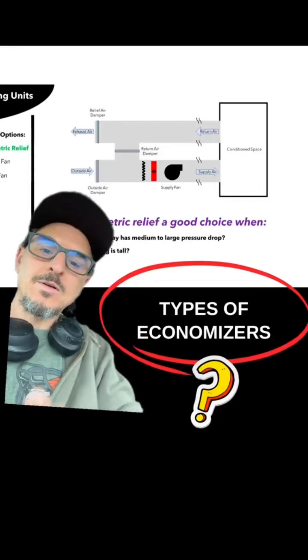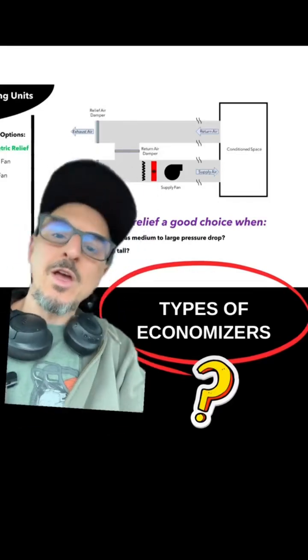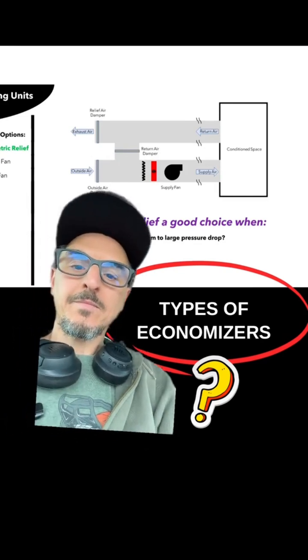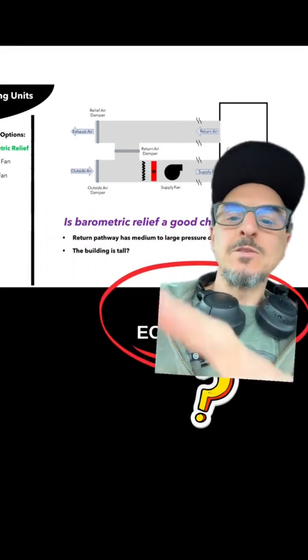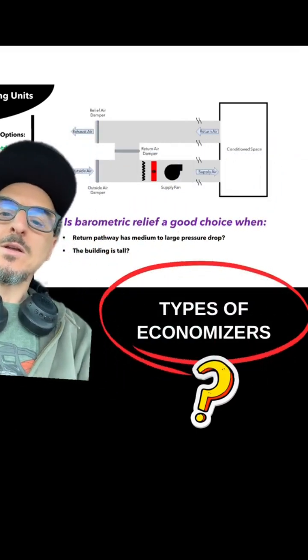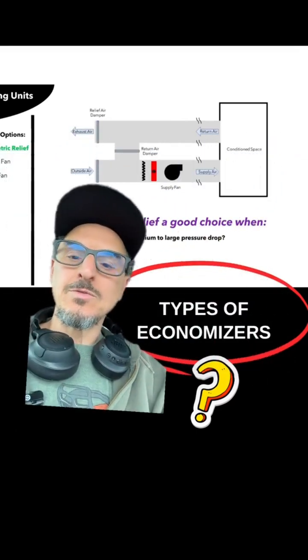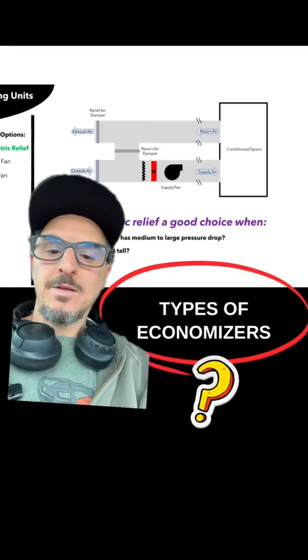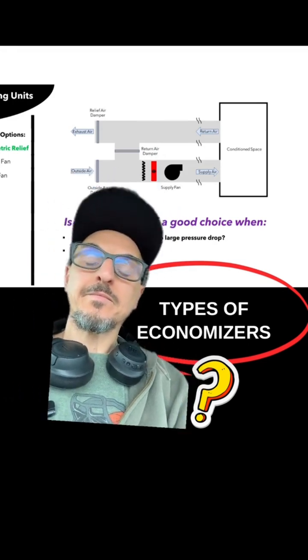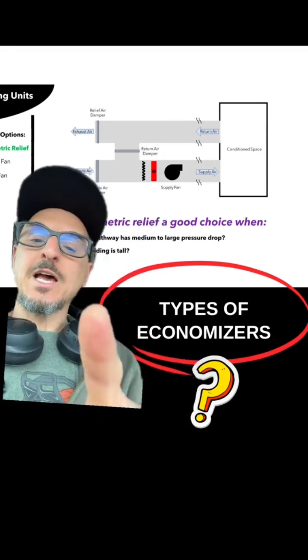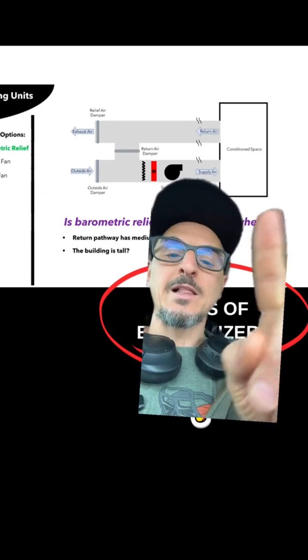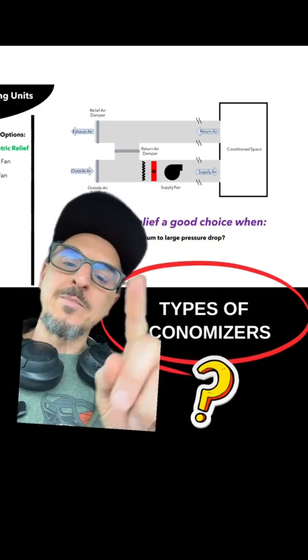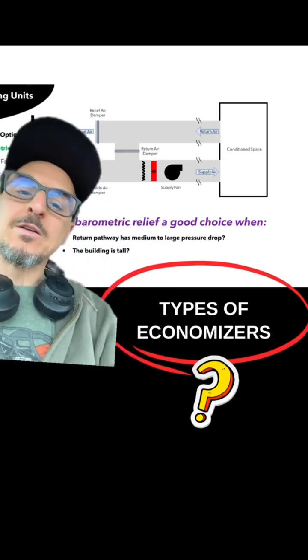In this video, we're going to delve into three different types of economizers. An economizer cycle brings in outdoor air when the conditions are right to use the outside air to cool your heat load in the conditioned space. For example, if it was 55 degrees out today and you were in an office building with a lot of interior load, you would open up your outside air damper, turn off your mechanical cooling, and use that air to cool the space.